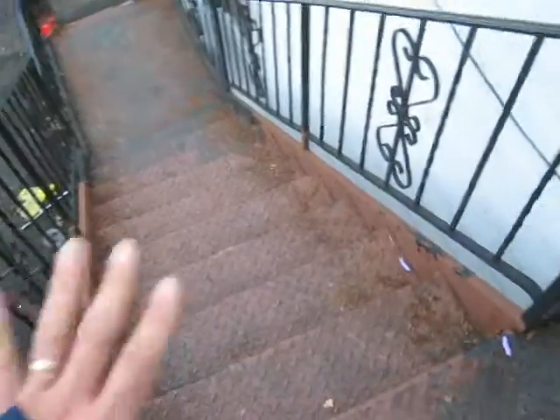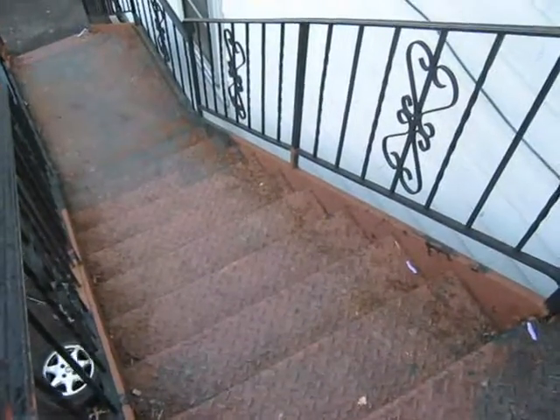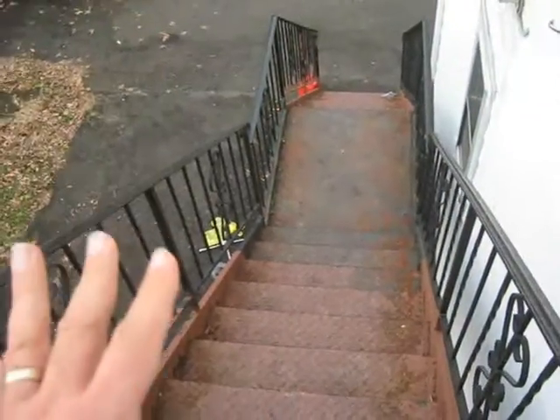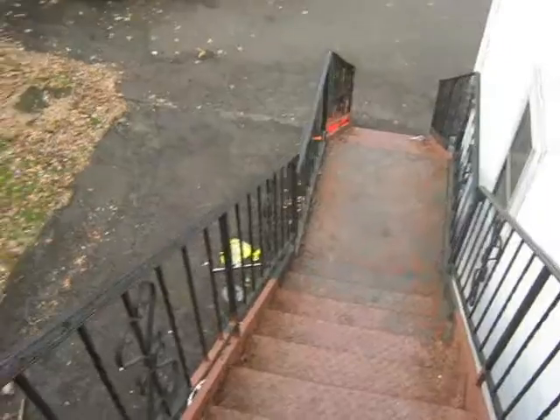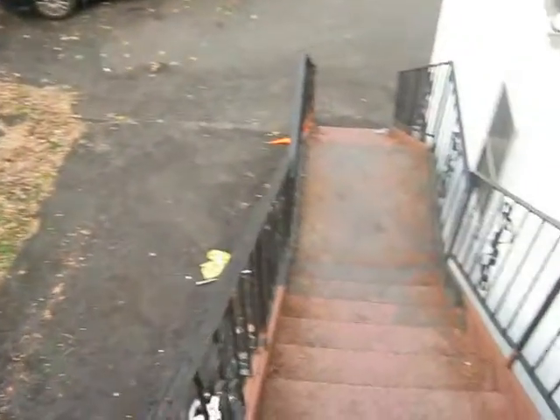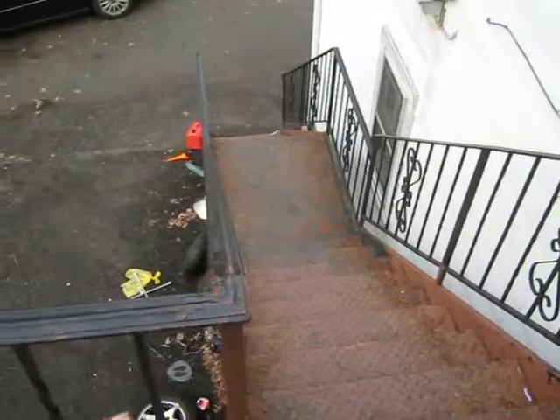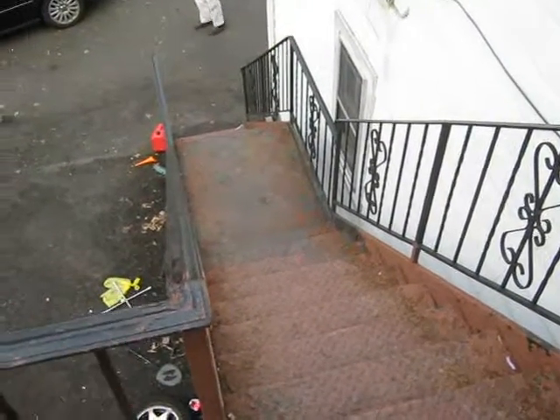Number two, we have lead issues. This fire escape is older than 1978, so it does have lead. So you have to meet two standards. The EPA requires that you have a renovator's license in order to touch this fire escape. Dealing with anything with lead-based paint, collect all the chips, make sure you don't contaminate the area. Your firm must be registered with the EPA, and you must have licensed renovators repairing, scraping, and painting this fire escape.